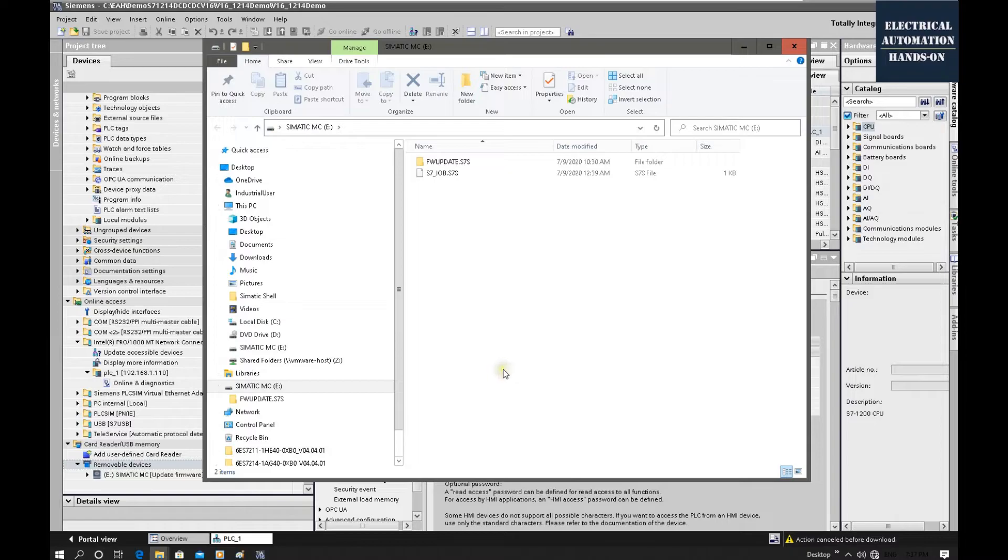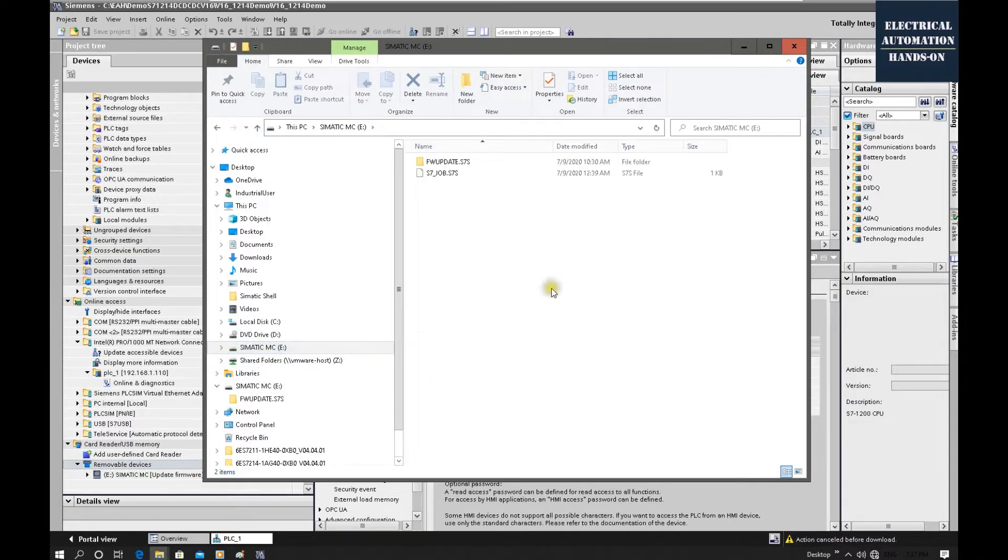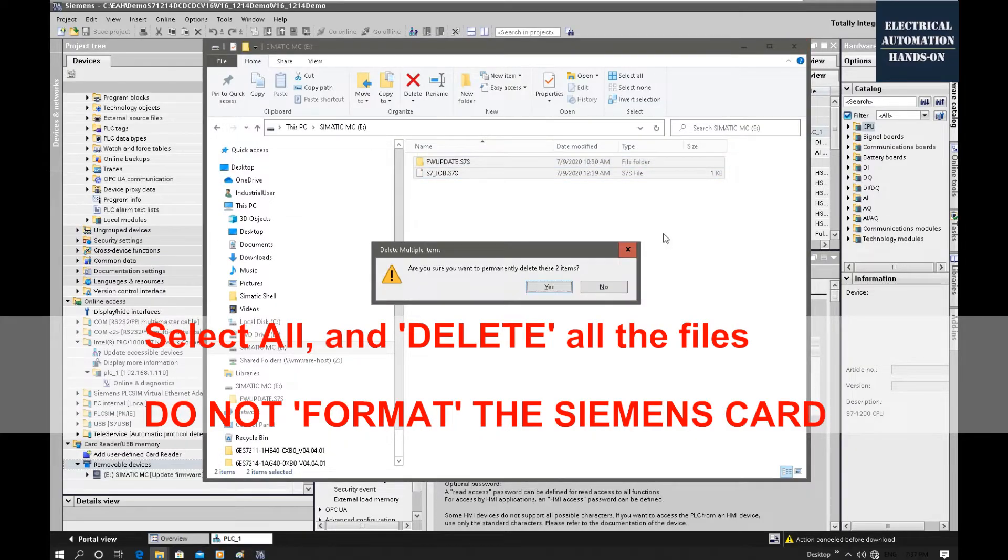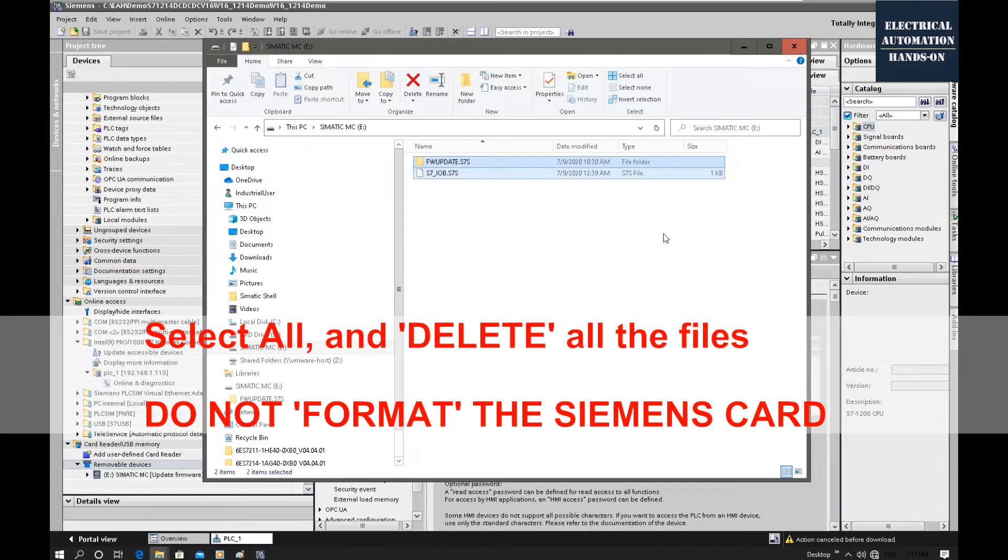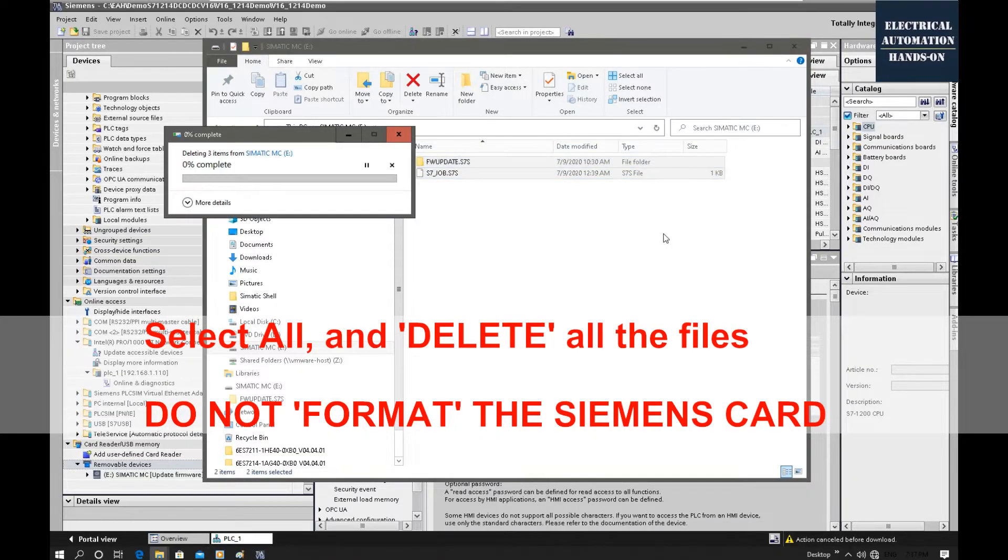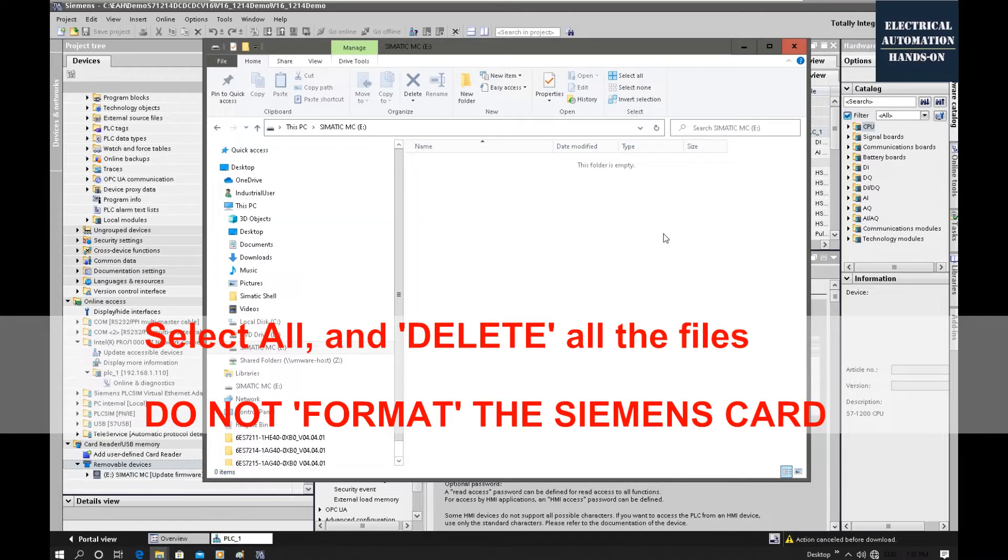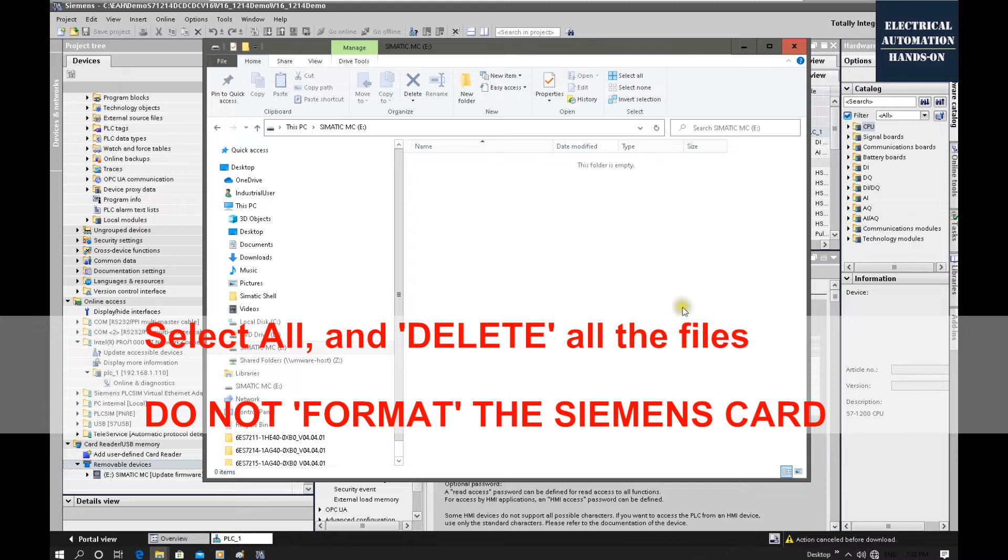Once your system identify this SD card, we can browse. Take care here. We need to delete all the file inside this memory card. Select all and delete. Keep in mind, you cannot format this memory card. Once you format this memory card, basically this memory card will turn to just a regular memory card. Siemens has a format inside. So you just need to delete all but you cannot format that.